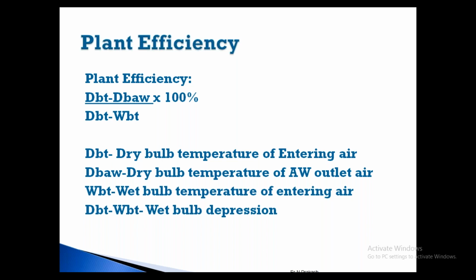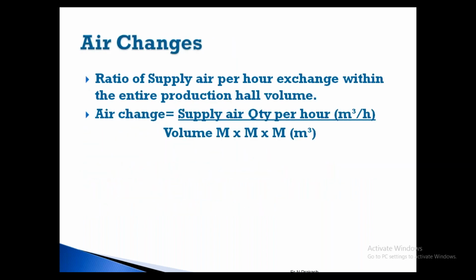So what is the optimum air change? You have to see that on a case-to-case basis. In any factory, you have to see the production rate, the speed of the machines, your back process, and the material flow. Based on that, you decide on the air changes. Just blindly people say, if it is spinning, I want this much air changes. That is not required. It is not that if you have one mill in the north, the same thing is followed in the south also. Based on your raw material, your material movement, your machine speed and your production process, you design the air changes.